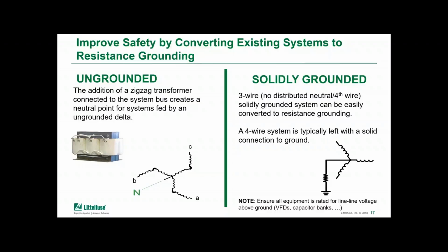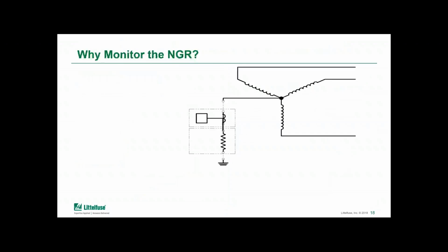What's not shown on here is a 4-wire system, but with those applications, if you have a distributed neutral for line-to-neutral loads, lighting is the most common one, those are more difficult to convert and usually would be left alone, or we'd need to take some additional considerations. In some areas, it is not allowed by code to resistance ground a 4-wire system, or there may be other specific requirements that have to be met. So that's something that needs further review.